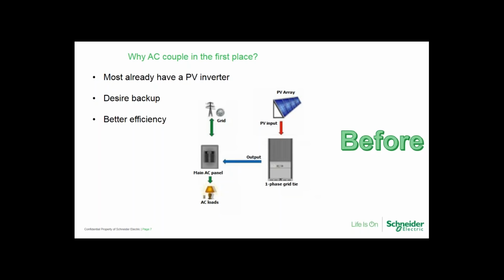The losses associated with DC coupling are the efficiency of the charge controller plus the efficiency of the inverter. This is typically around 90% when you add the two. Grid interactive inverters are typically above 96% these days. So how will the system change by AC coupling is the question.